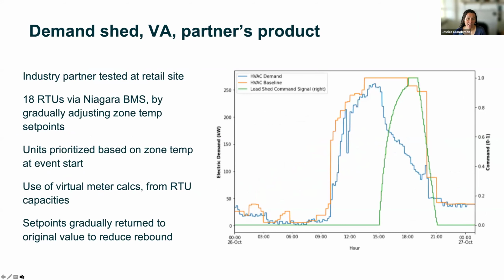This is a second example, working with a partner who put this into a different product environment and tested it at a retail site in Virginia. So this was 18 rooftop units interfacing with a Niagara building management system, again using the zone temperature set points. In this case, each of those 18 units was prioritized based on zone temperature at the start of the event. The calculations here for demand are based on virtual meter calculations that include the known capacities of the units. Again, there was a stagger back to avoid rebound.